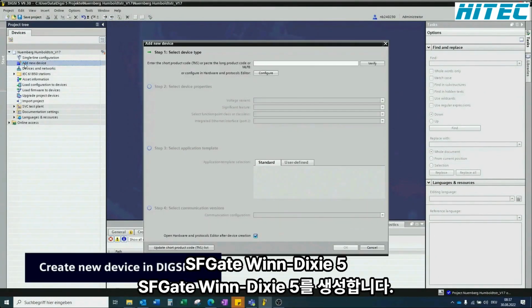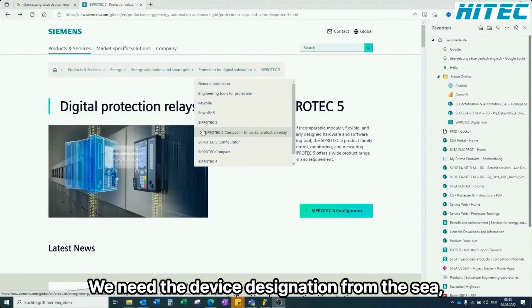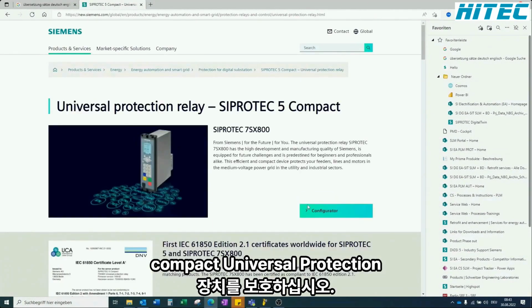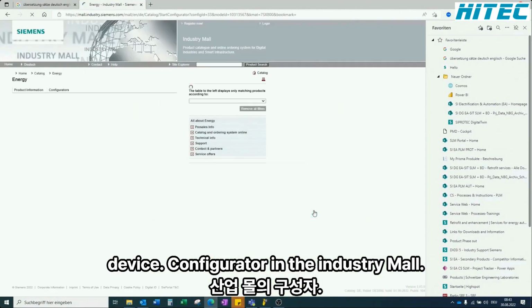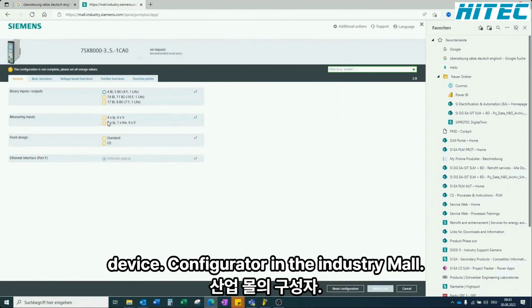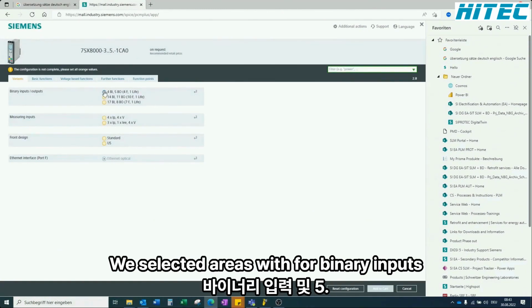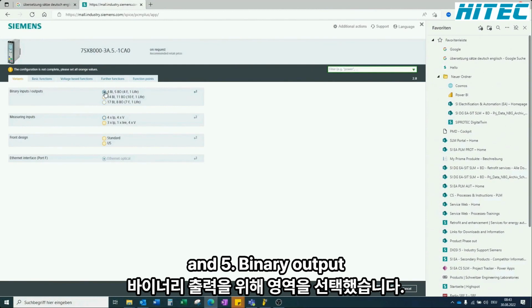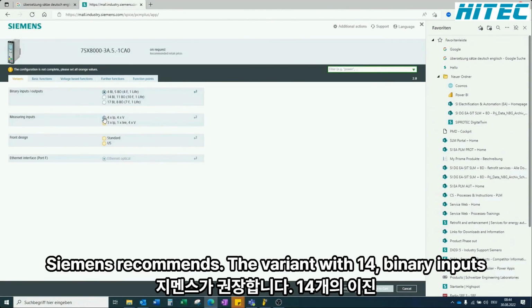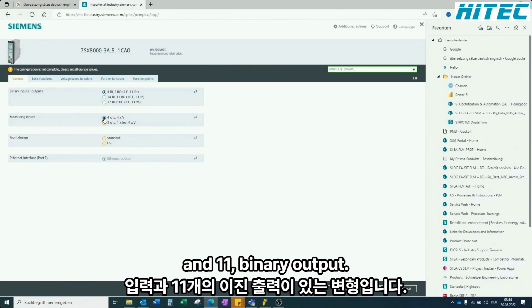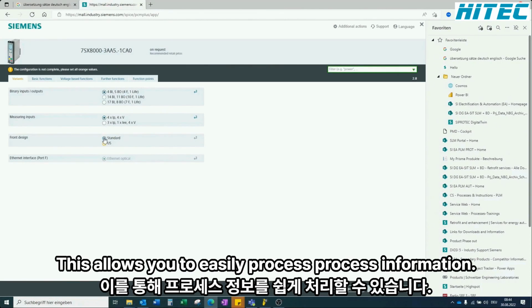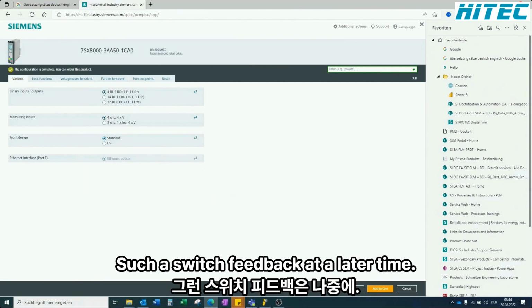In the next step, we create an adequate SIPROTEC 7SX800 in DIGSI 5. For this we need the device designation from the SIPROTEC 5 Compact Universal Protection Device Configurator in the industry mall. We select the variant with 4 binary inputs and 5 binary outputs. Siemens recommends the variant with 14 binary inputs and 11 binary outputs. This allows you to easily process information, such as switch feedback, at a later time.